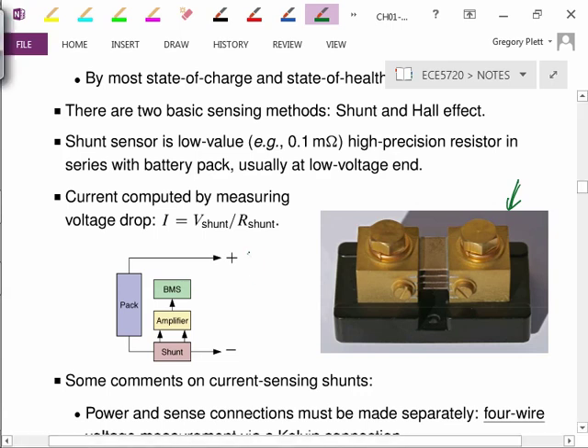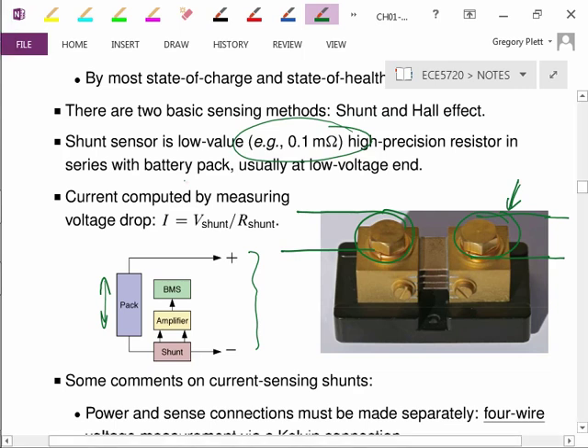In this schematic diagram, I've got the battery pack, this is my high voltage set of cells, and my plus minus go to the load, and I've got a battery management system and so forth. The shunt is placed in series with the load. I've got an enormous cable bolted on there going to the battery pack and another enormous cable going to the load. All of the load current passes through this resistance. It's a very low resistance, usually on the order of 1/10 of a milliohm. This one here is 1/10 of a milliohm resistor.